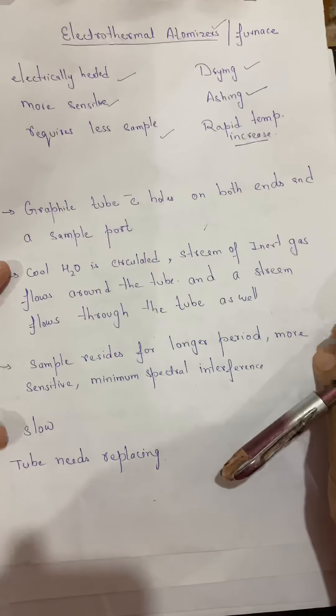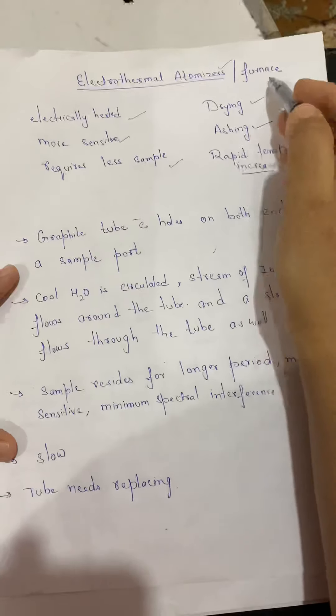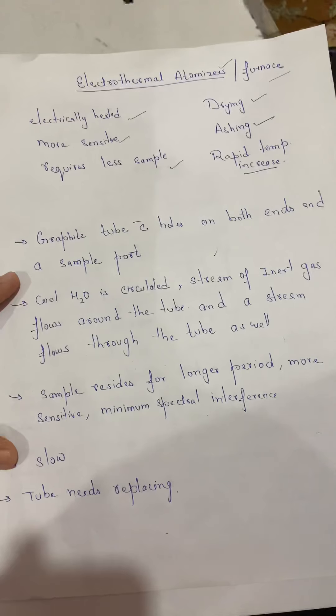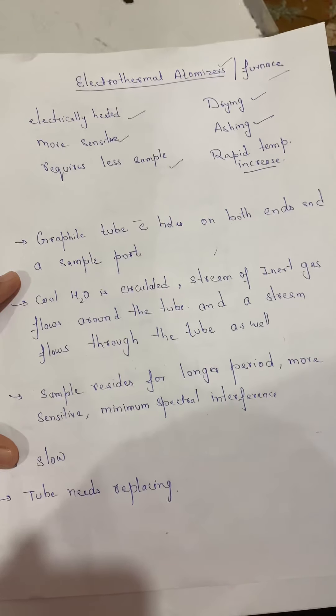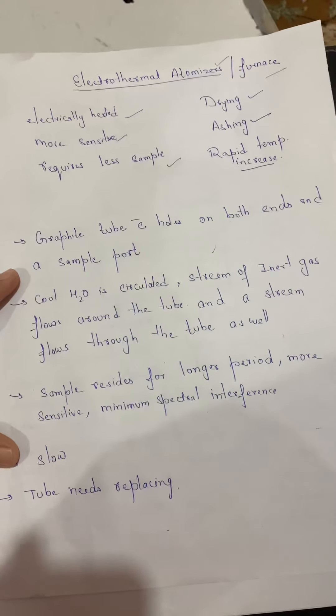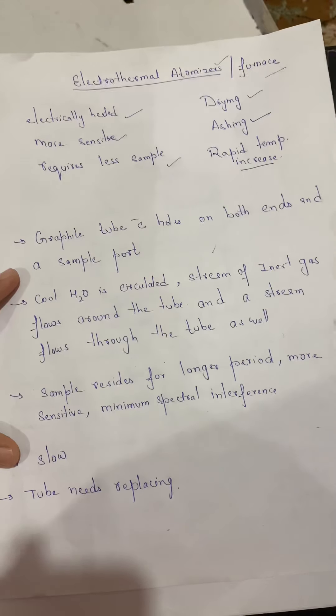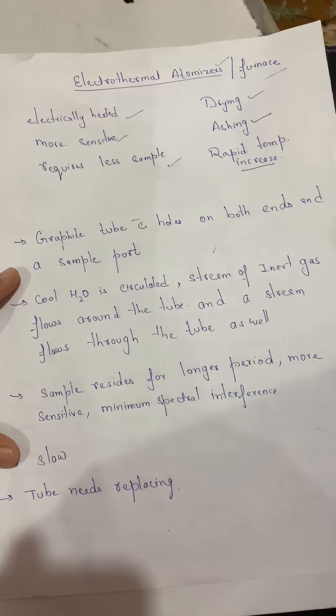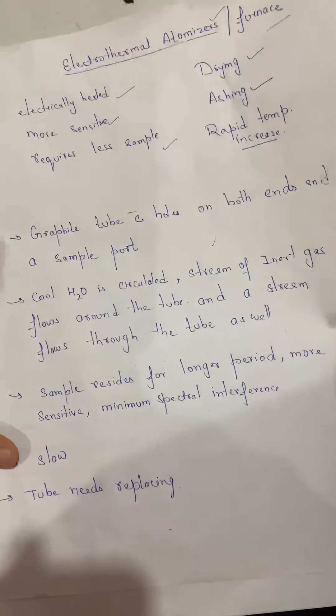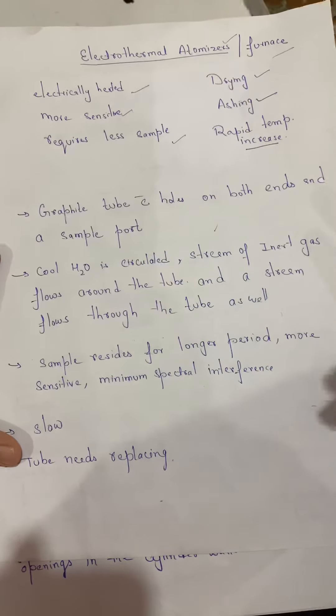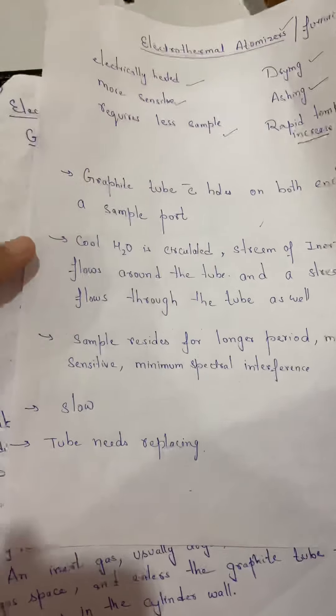Today we are going to study another type: electrothermal atomizers, also known as electrothermal furnaces. These are electrically heated — the sample is heated using electricity to such high temperatures that it gets broken down and dissociated into an atomic state. These atomizers are more sensitive and they require less sample in comparison to flame atomizers.